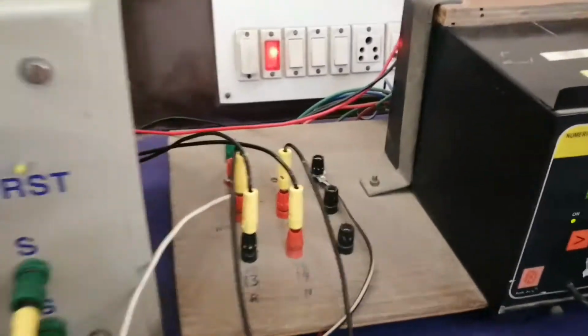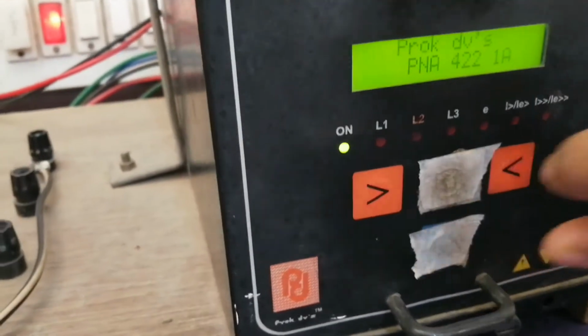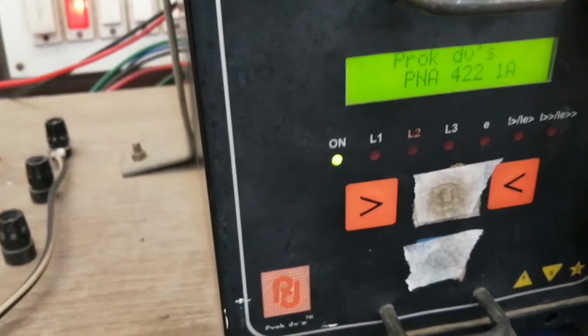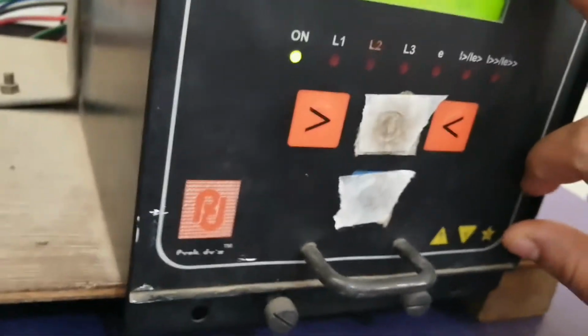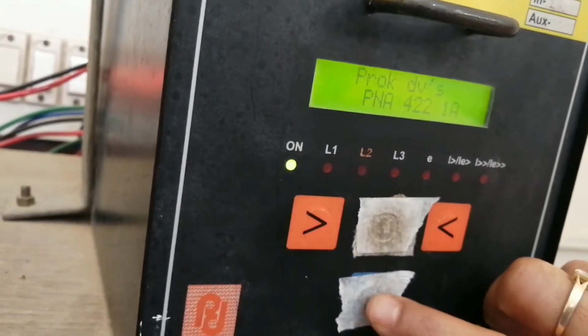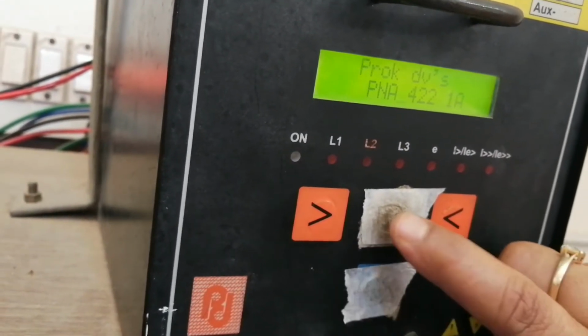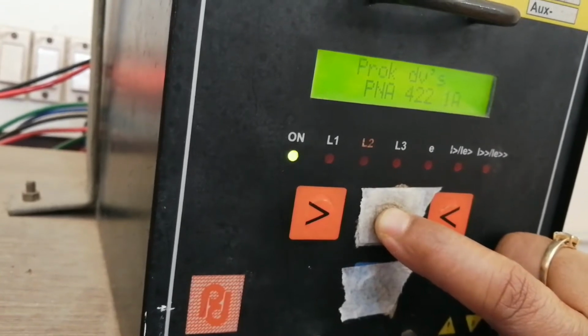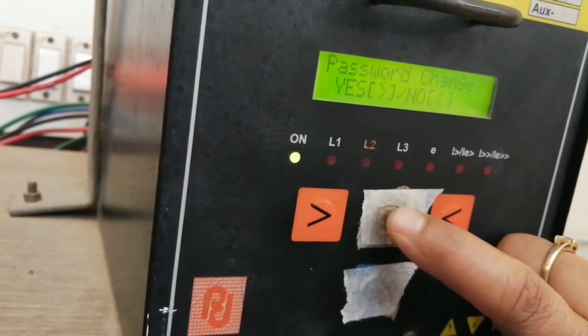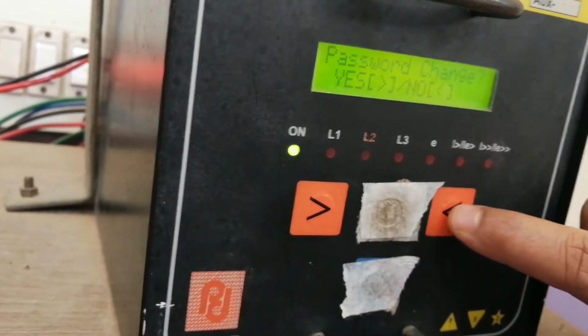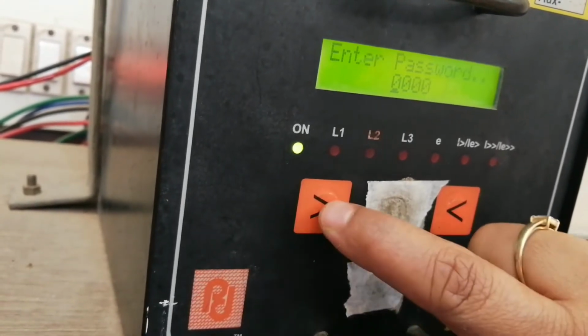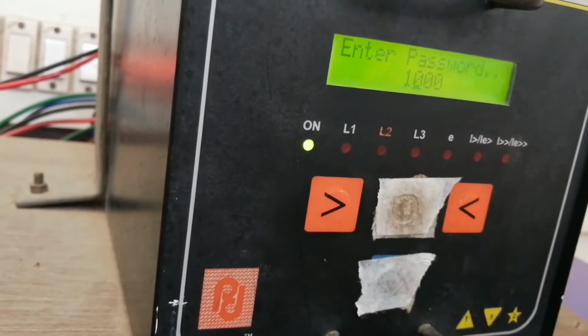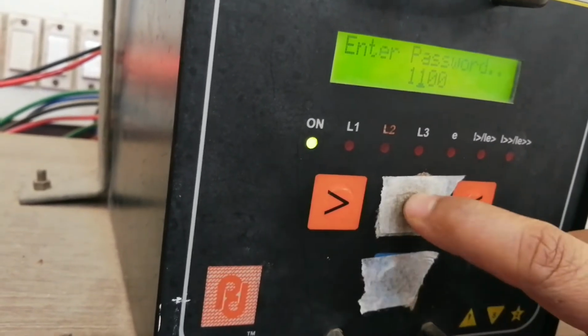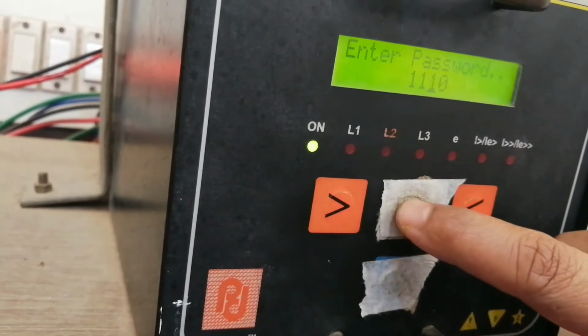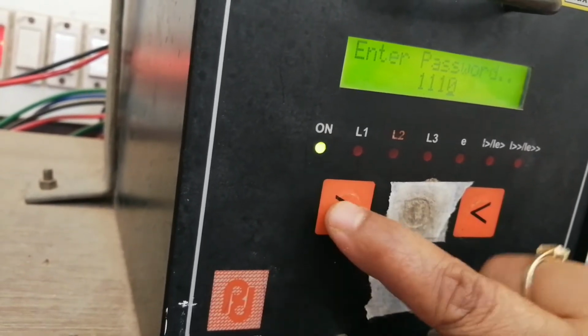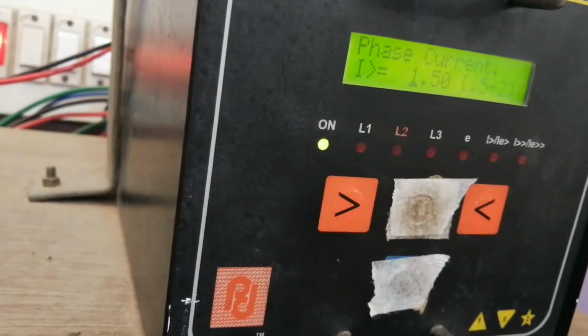Before starting conduction, you have to know the settings of this overcurrent and earth fault relay. It's very, very important to know these settings. How to start this earth fault relay: press this button once, then press and keep a long press. Password change. I'm not changing. Enter my password: one, enter, one, enter, one, enter. So I have entered the password.